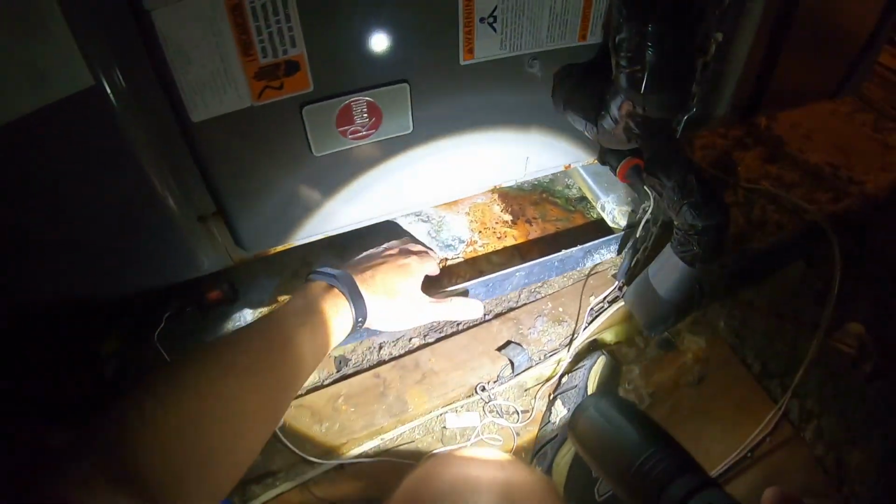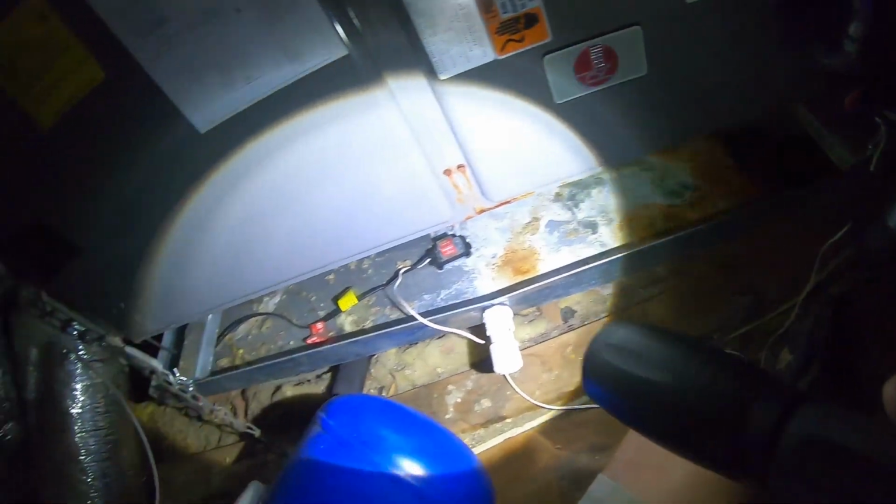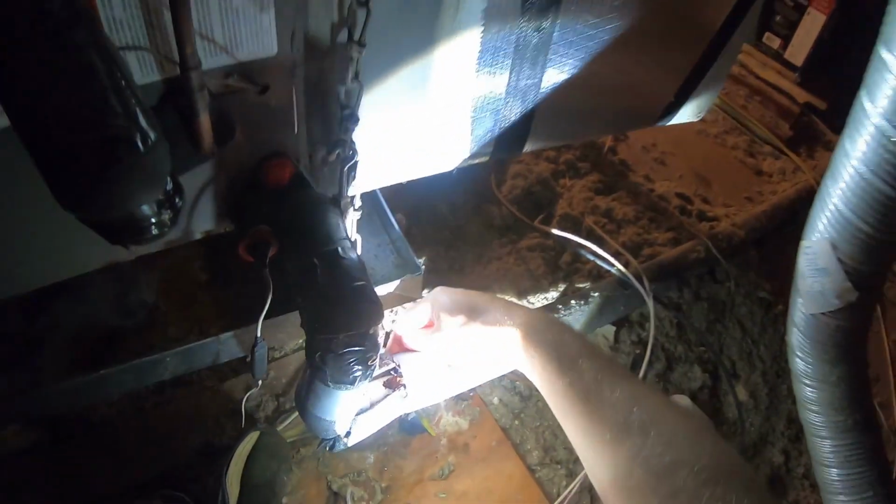Now, I mentioned before that if you're doing this with a garden hose, you've got to be really careful. The reason is that it's very easy to overflow this primary pan in the bottom of this unit and fill this pan with water. Then you trip your sensor. Oh, a little cucaracha there. Nice. So I believe I left a slip fitting right in here. Somewhere in here. Yep, right there. Just bend that up.